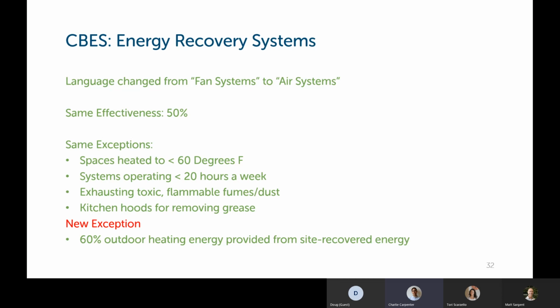If a space is heated to less than 60 degrees or it's operating less than 20 hours per week, you do not need energy recovery. Also, if you are exhausting toxic or flammable fumes and dusts from a space, you do not need energy recovery. Or kitchen hoods that are removing really heavily grease-laden air do not need to have them. A new exception that's been added is that if 60% or more of the heating energy is provided from site recovered energy, then you do not need to have an energy recovery system. Next slide.